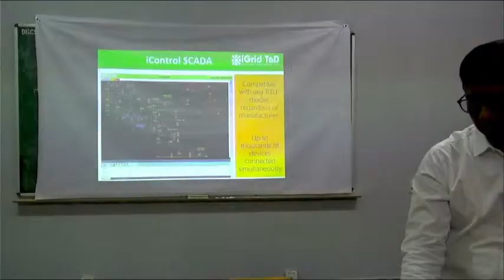What about the different line color indications? It's called line coloring, showing whether the bay is charged or not charged, and I can define those colors. We'll show you live with this SCADA - if the breaker is red it means it is closed, if green it means it is open. We follow different standards like that, which indicate the status of the substation.